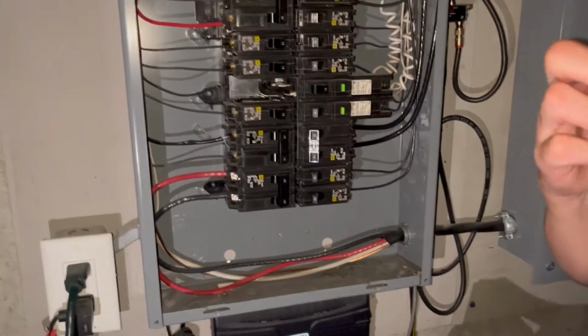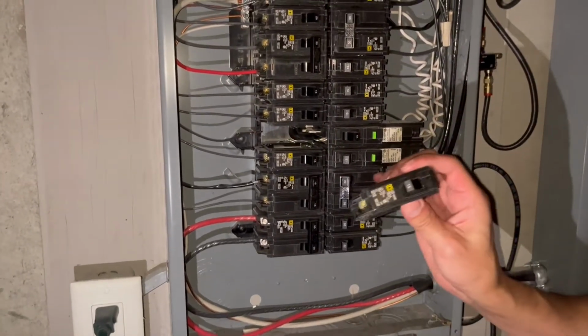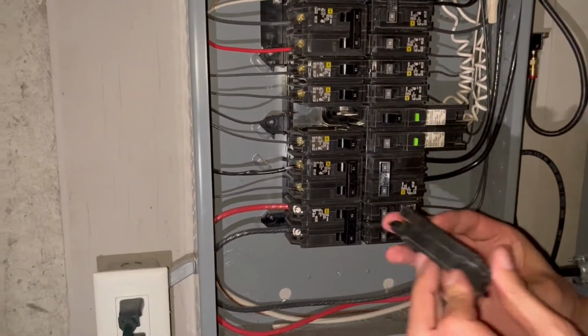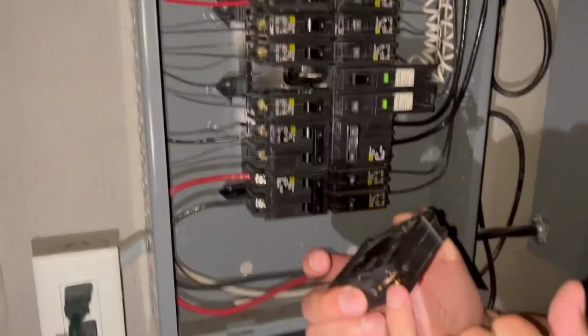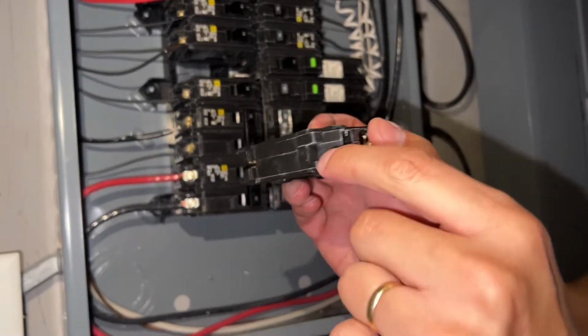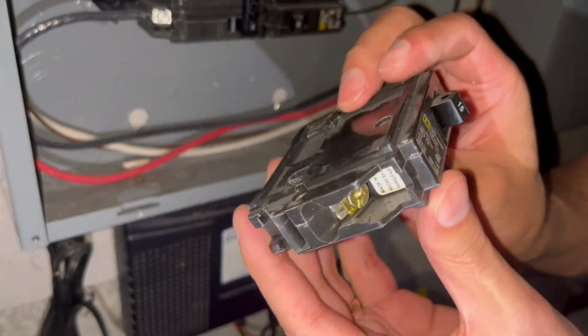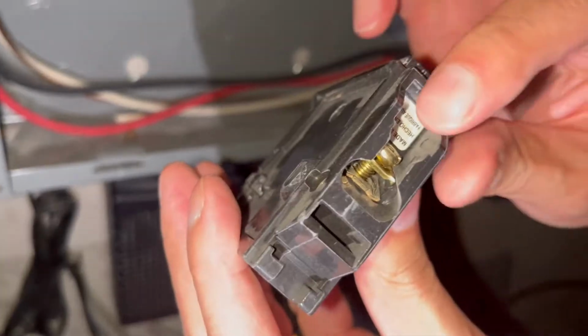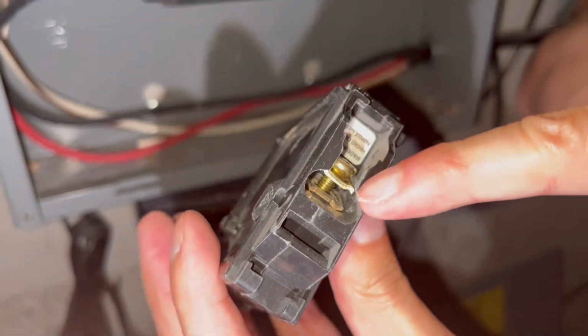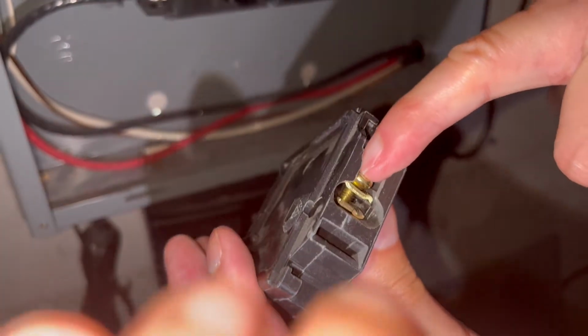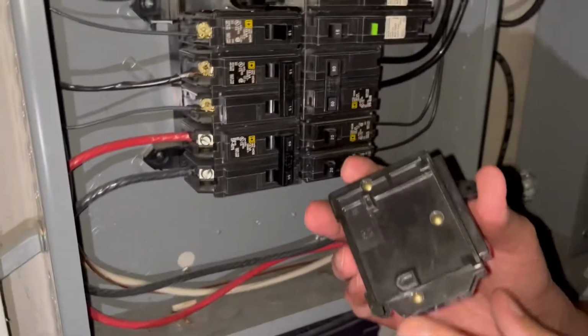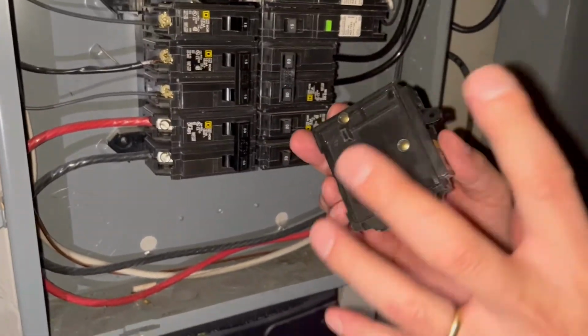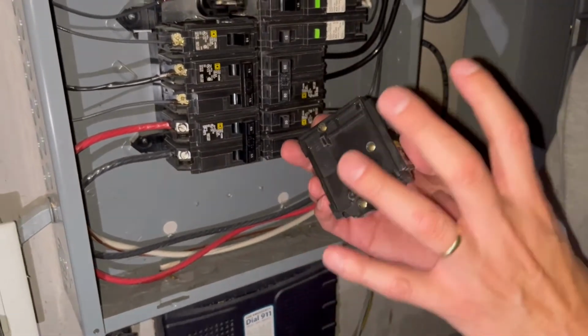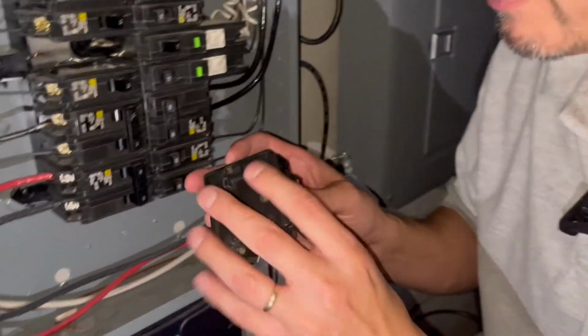Okay, guys, we've removed the damaged circuit breaker. We're putting the brand new circuit breaker in. The connection point on that, that's what the snap-in looks like. And this is kind of what the hinge part looks like. Also, if you want to see a close-up of the screw, there you go. That's your wire assembly. That's where the hot black wire will go into, and we're simply going to attach it on down. A circuit breaker is nothing more than a mechanical device that replaces fuses. It protects the wiring in your house so they don't overheat and draw too much power.